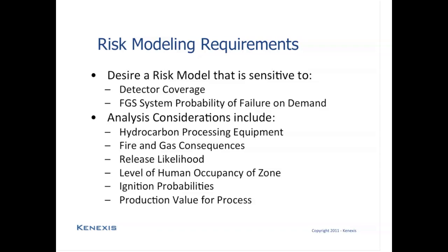Then we're also going to want to look at things that drive the overall risk, but are outside of the actual loss of containment event. Things like what degree of occupancy is there in the zone that's under study? What are the probabilities of ignition if gas releases occur? And then also you might want to consider things that go beyond safety in your fire and gas system design, such as the production value of the process. There is value in providing fire and gas system protection simply to avoid large commercial losses and not just looking at the personnel safety attributes of fire and gas system design.